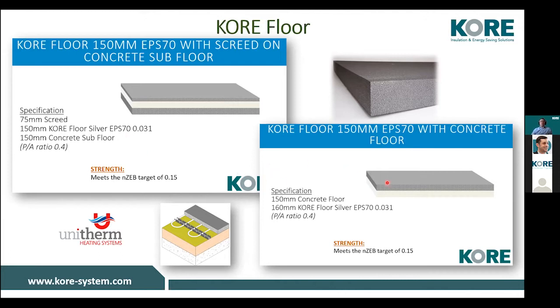Looking at a different type of buildup, where we might have a concrete slab straight onto insulation. And again, we have the same perimeter area ratio, 0.4. We'll need 160 mil for that buildup of our EPS 70 silver. Again, to hit that target of 0.15, where we're using something like underfloor heating. And again, because it's an EPS, it works very well with the underfloor heating system. So they're just a couple of examples.